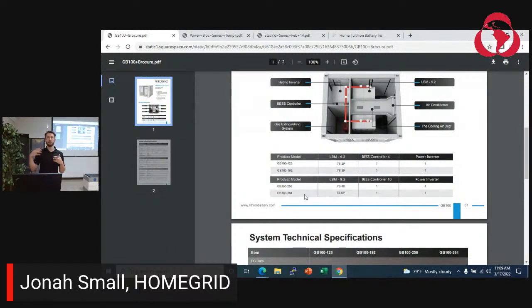If you're working with different voltages, we can integrate isolation transformers to change them around. We have projects in Canada working with 600 volt three-phase on larger solutions. Our last product is a 20-foot container that can go up to 1.1 megawatt hours with a 500 kilowatt inverter. We also have projects elsewhere operating on different voltages, so we can accommodate those.